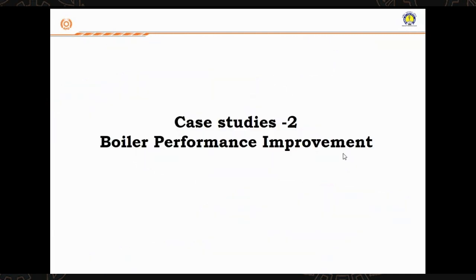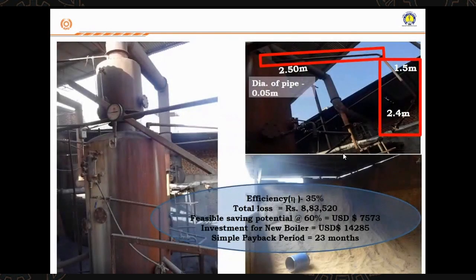Now, this is one of the cases done in Nepal. This boiler, if you see, has no insulation. The boiler is running with risers, there is no insulation. It's very bare pipelines, and the efficiency of the boiler is as low as 36%. We were shocked to see how this boiler can run at 36%. They know the technology, but sometimes the capex is the problem.